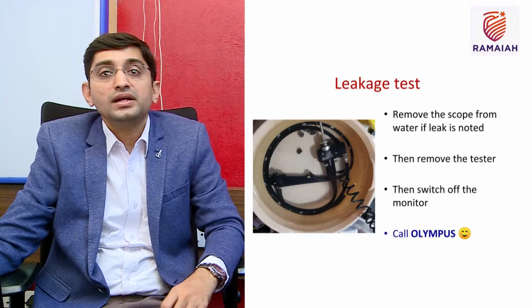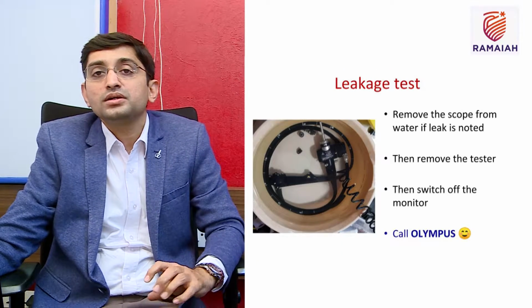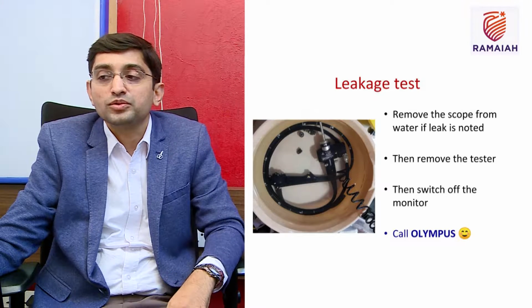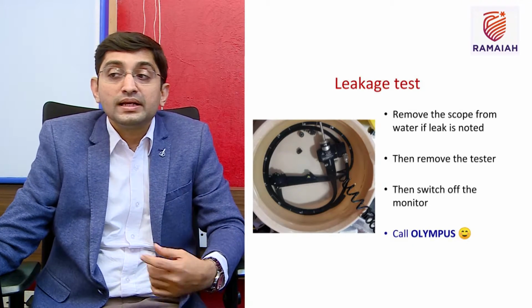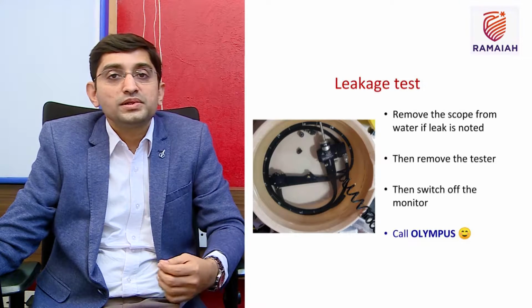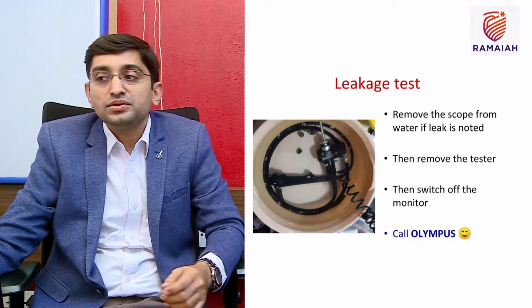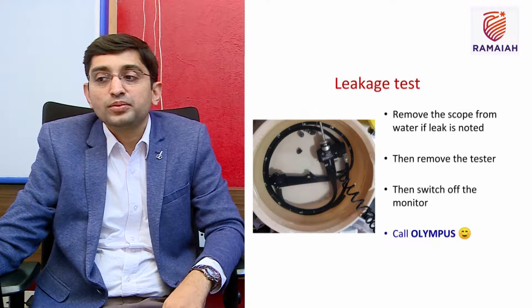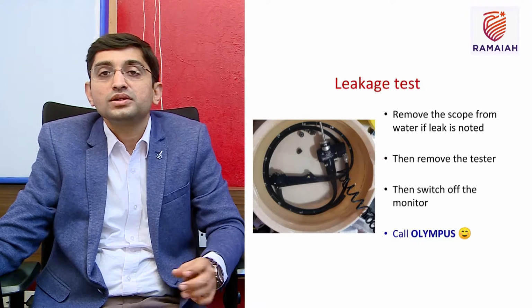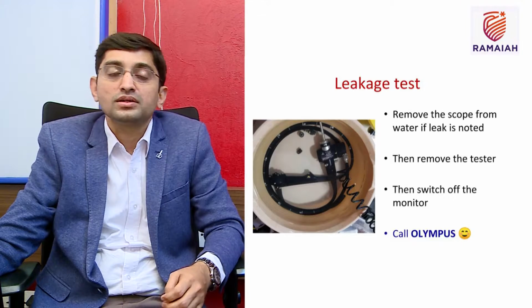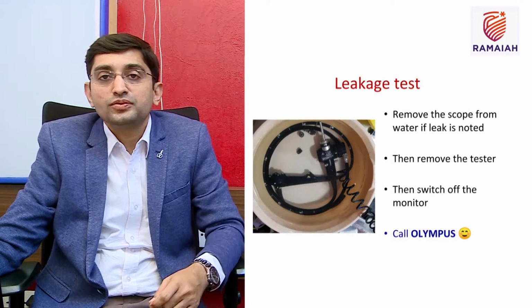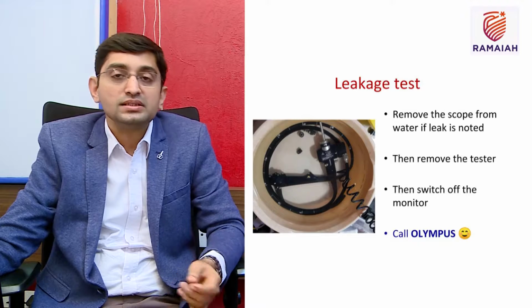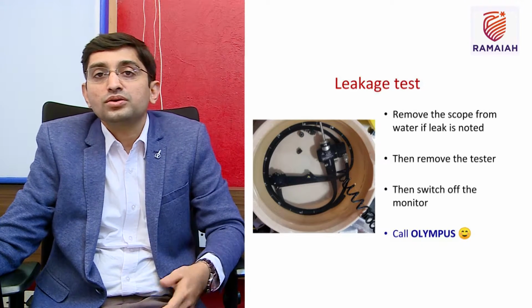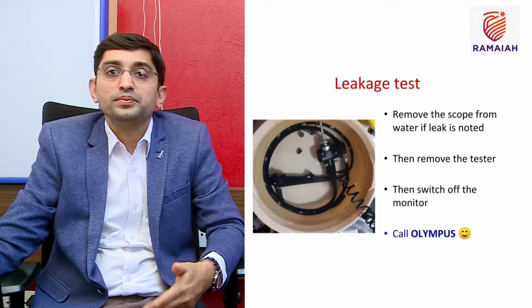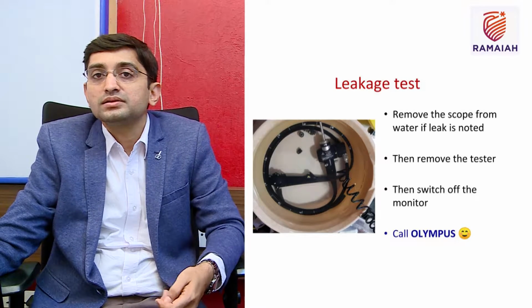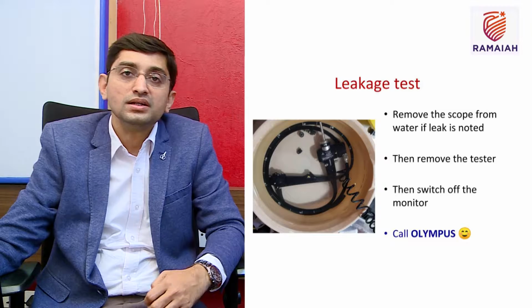If bubbles are noted, immediately remove the scope from the water. Don't keep on looking at the bubbles. Once the scope is removed from the water, that is, the leak is positive, you remove the tester from the scope. That is very important. Don't switch off the monitor immediately, because there will be a suction type of effect. So once you remove the scope from the water, then you remove the tester, then you switch off the monitor. And then you call the company person, Olympus or Pentax, for taking the scope for repair. So that is for the leakage tester.